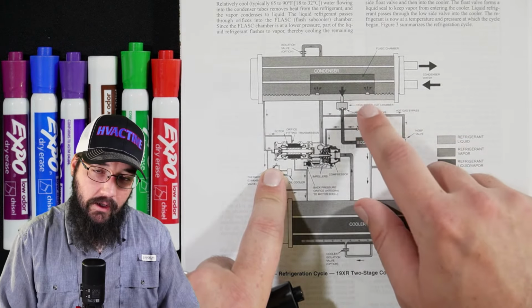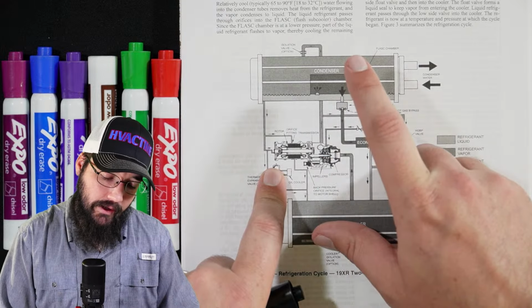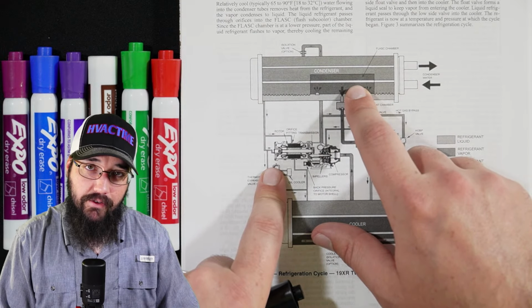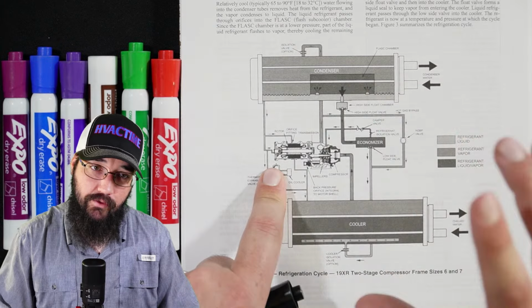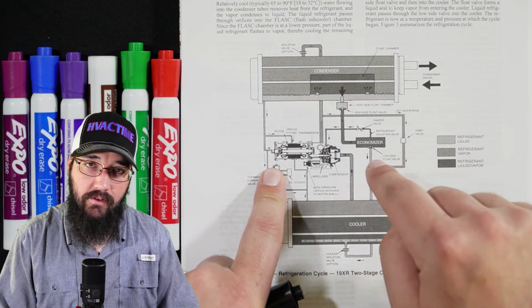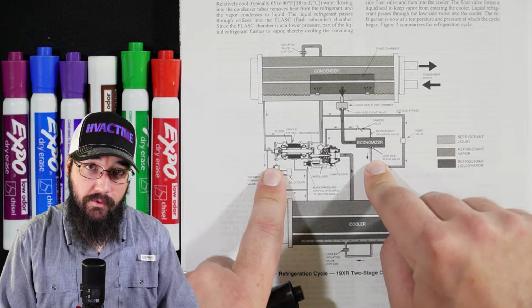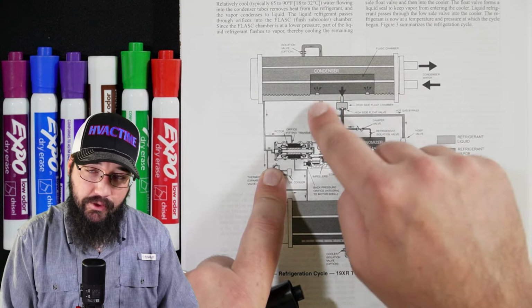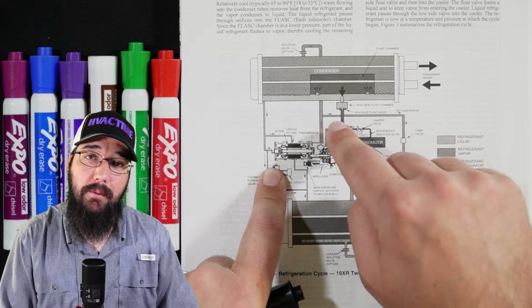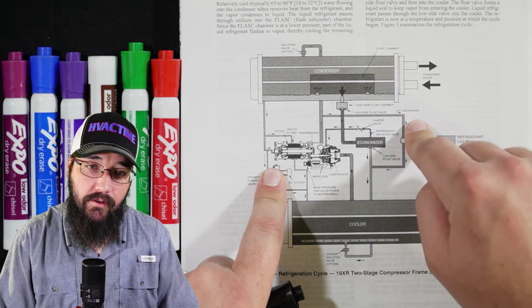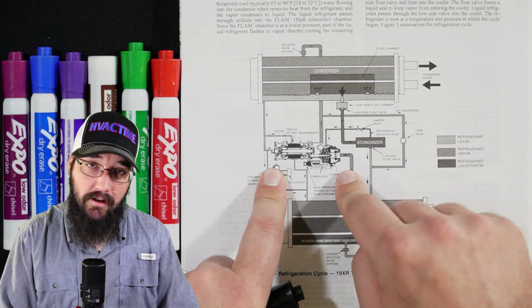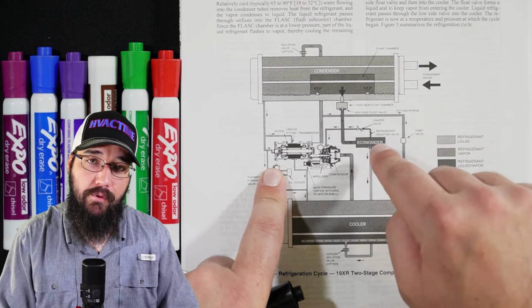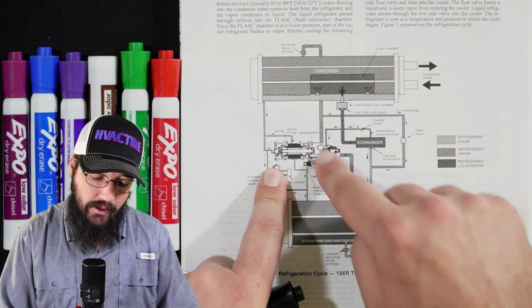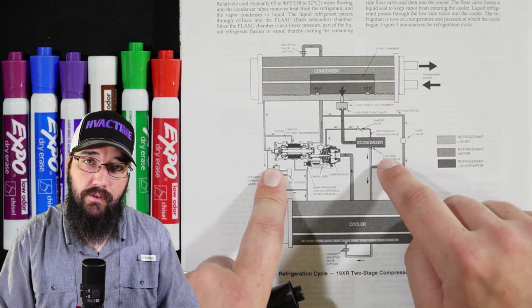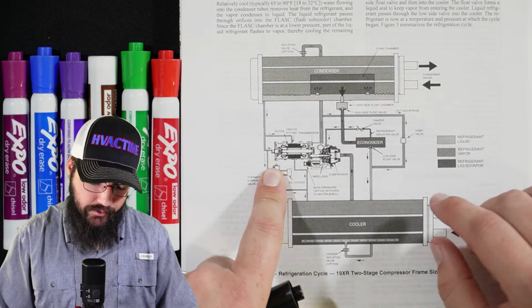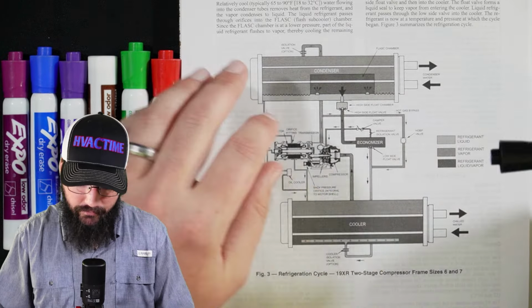Even in the other style with just a single stage compressor, they will still reference this as the flash chamber, not the economizer. So just understand that if you're reading this material or you're trying to research this material on your own, these definitions matter, and it can be the difference of finding what you need to know so you understand, and not finding it. If you don't have the proper terminology and understand what's happening, you're not going to be able to reference this material correctly, and that's where you're going to struggle, right? That's why I harp on this so heavily.